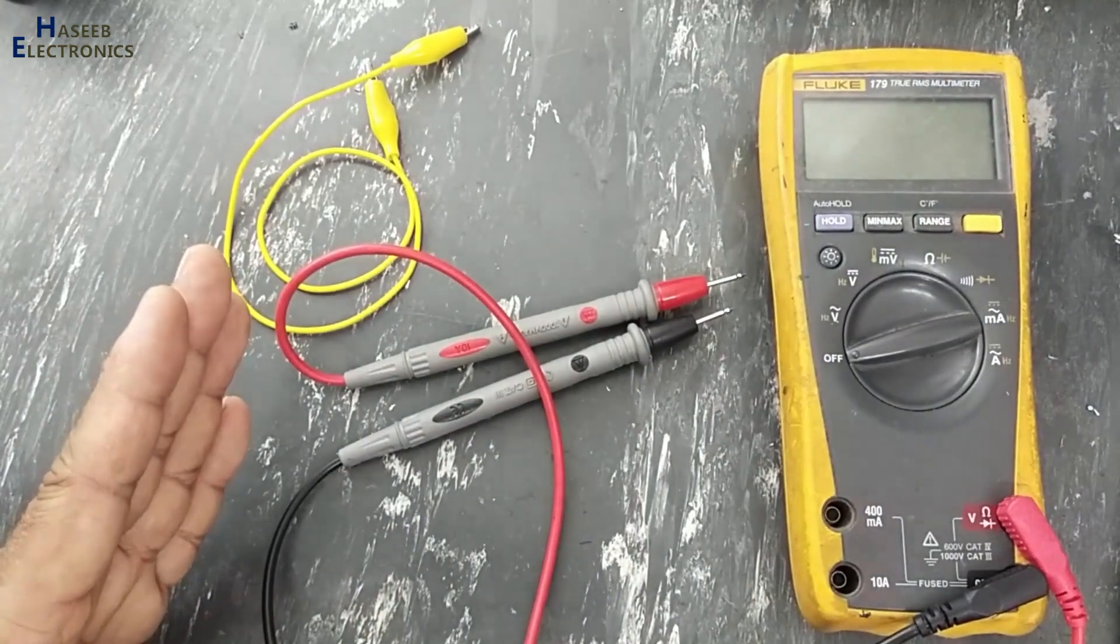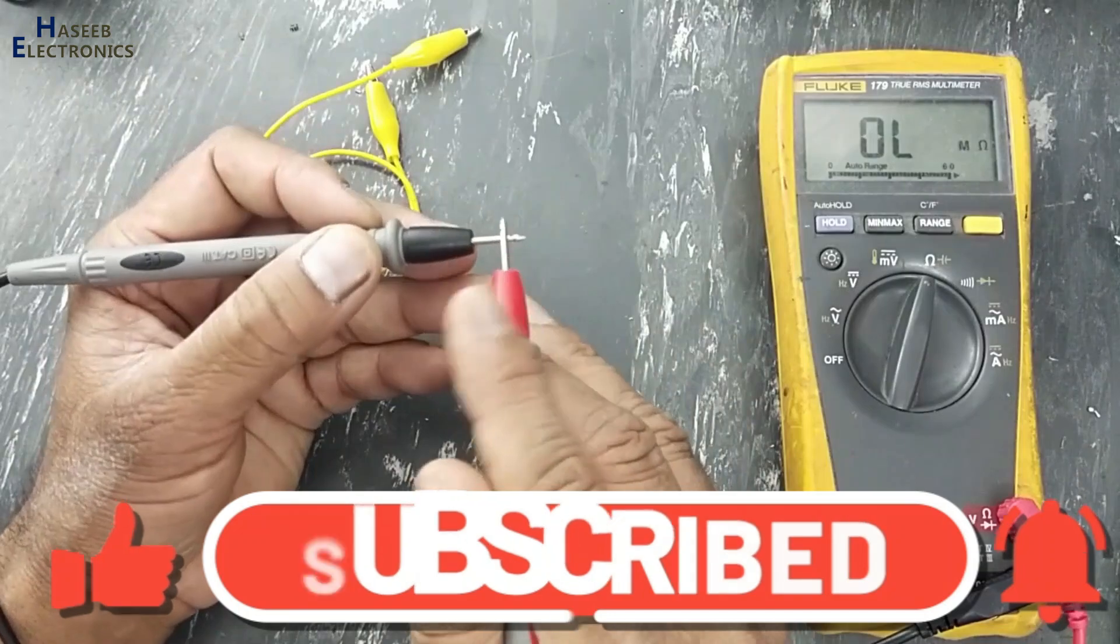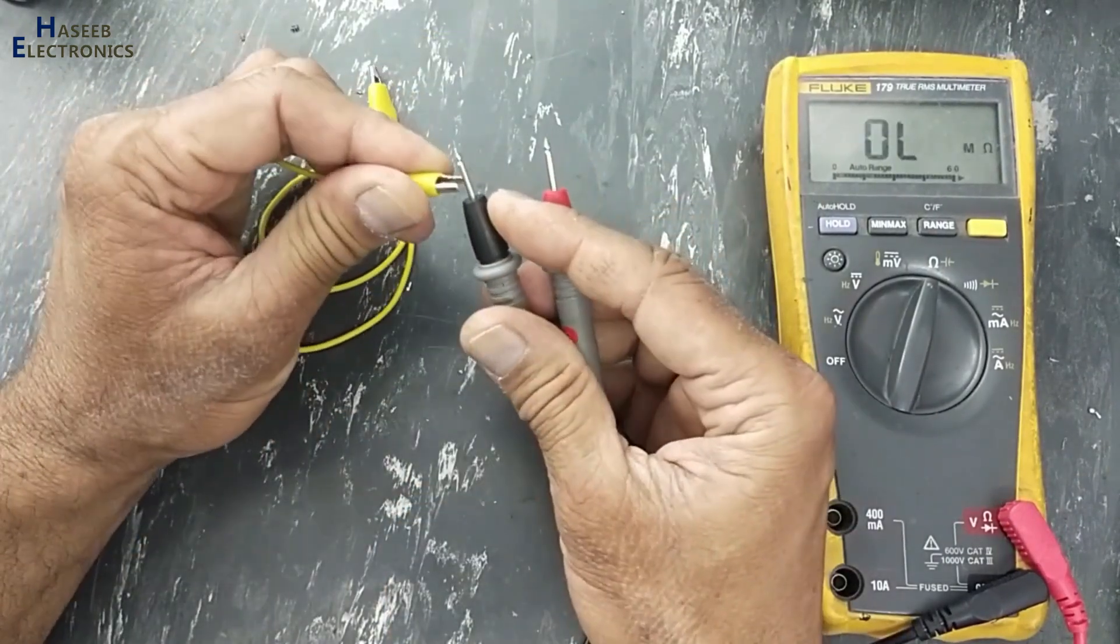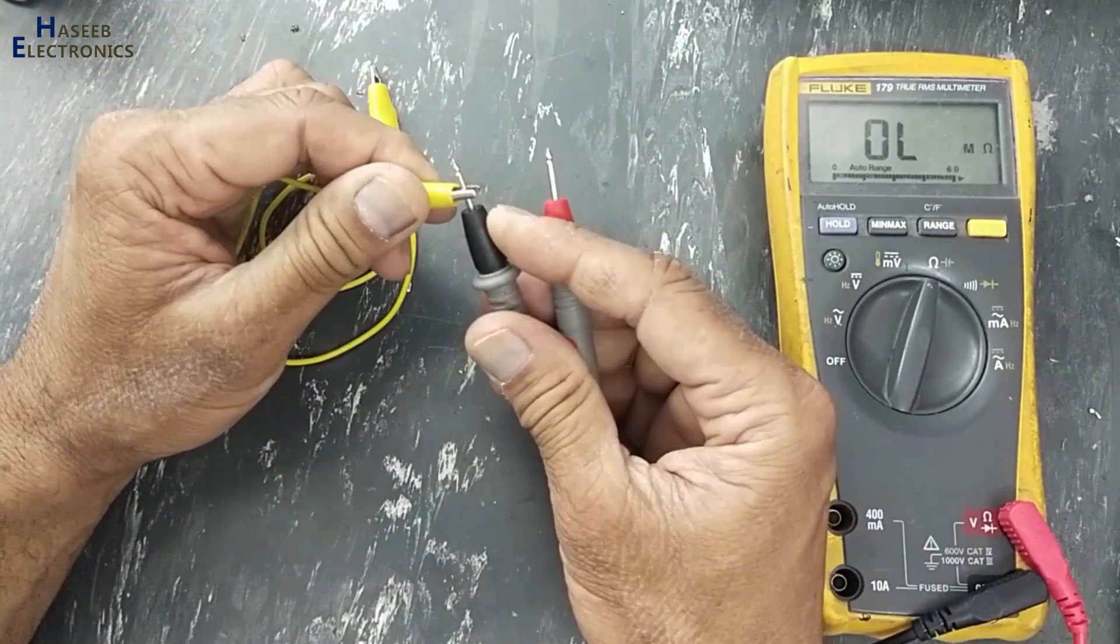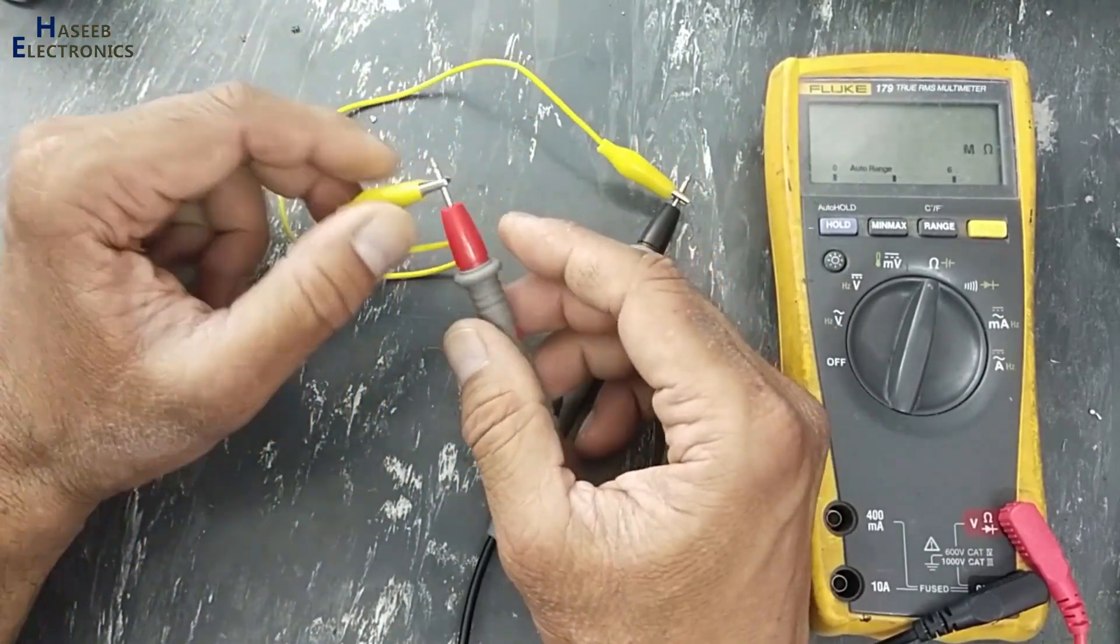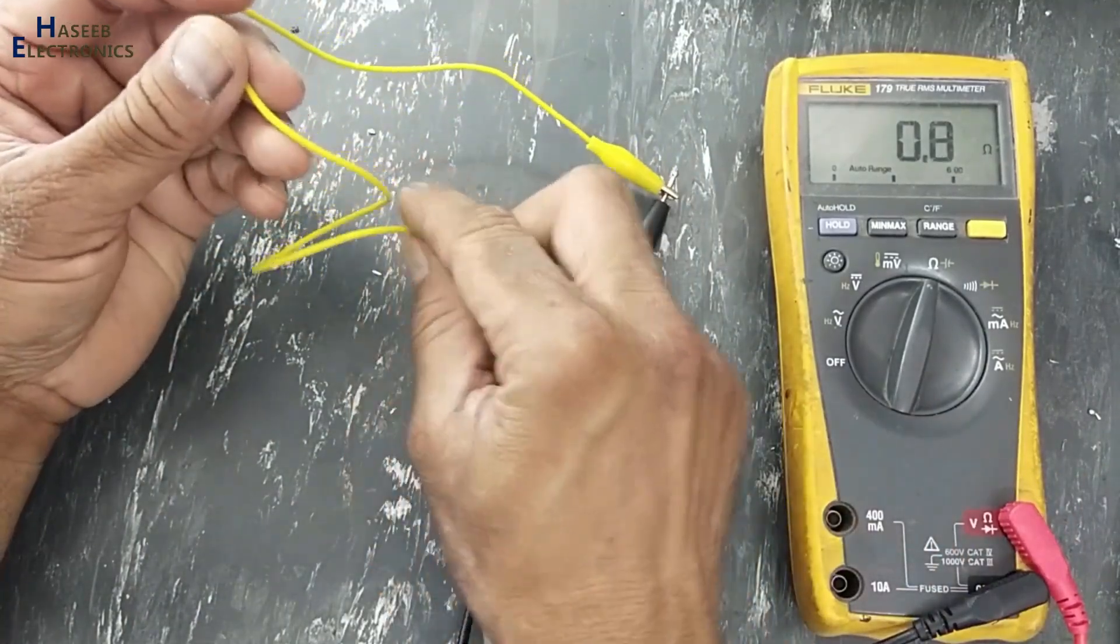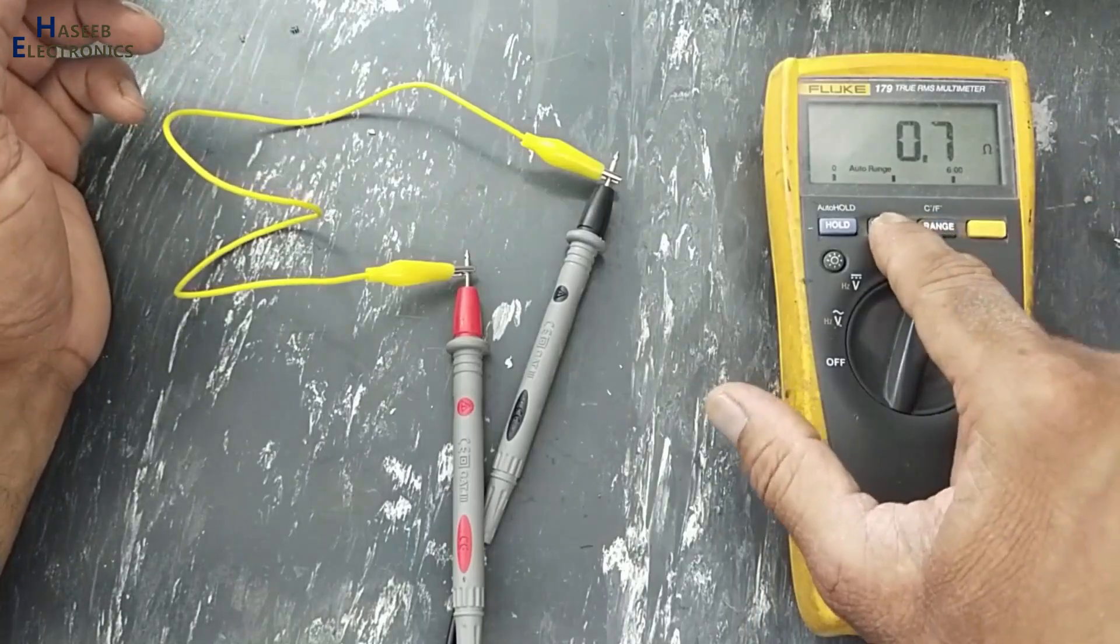The best option to record these changes is using the minimum-maximum option in resistance mode. If I want to test continuity or resistance of this wire, it may be any circuit.